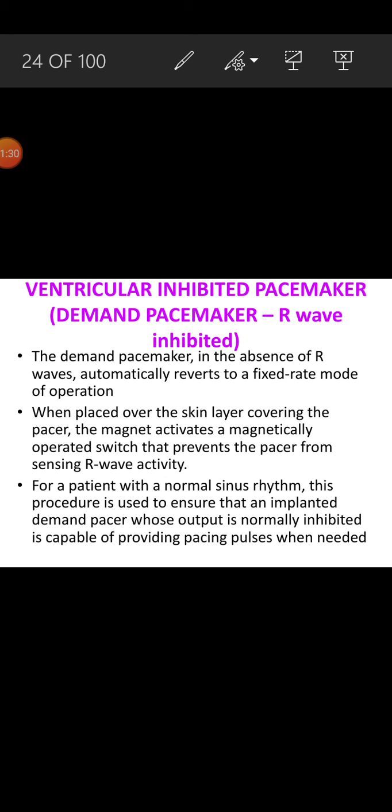Some external demand pacemakers have a sense pace indicator that deflects for each detected R wave or pacer initiated impulse. The on-off switch of some external pacers is provided with an interlock mechanism to prevent the unit from being accidentally turned off. So a demand pacer, in the absence of R waves, automatically will revert to the fixed mode.